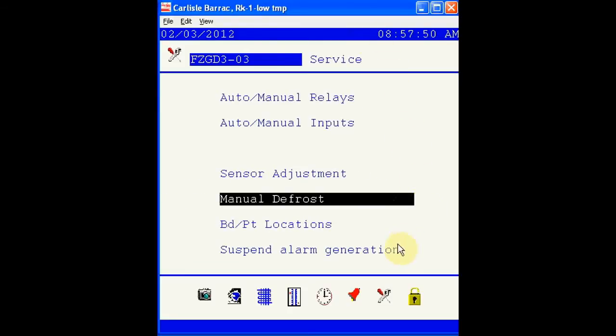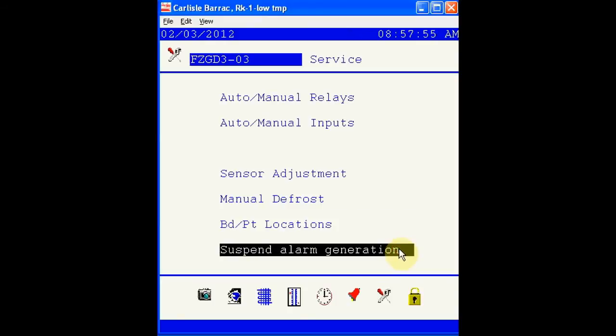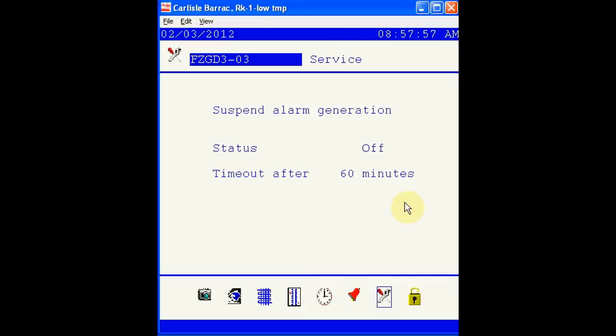Next, let's look at the option of suspending alarm generation per sensor. In this case, if we switched the status from off to on, this case would be suspended for 60 minutes, allowing no alarms during that time. After 60 minutes, the normal alarm generation possibilities would exist.